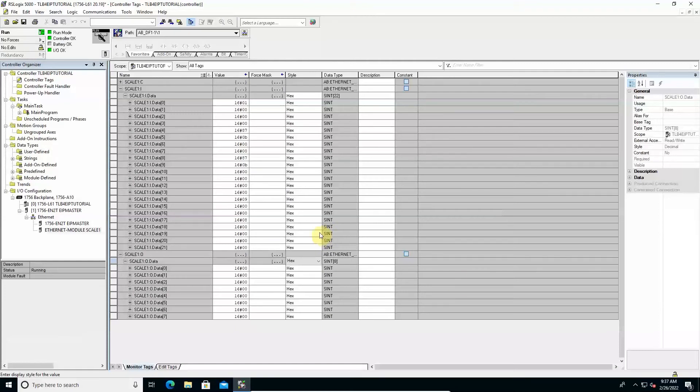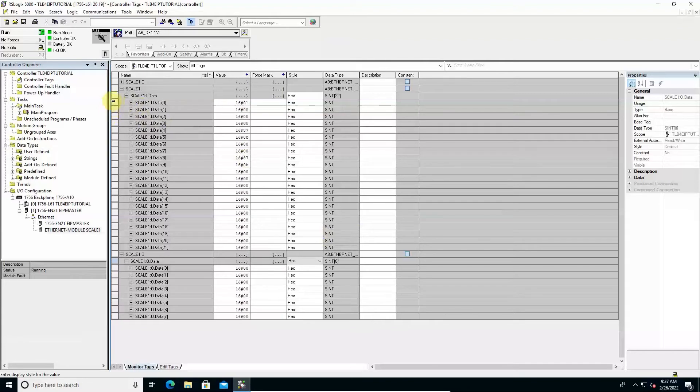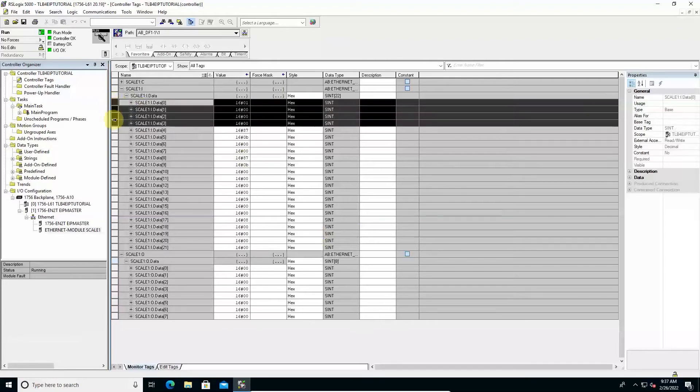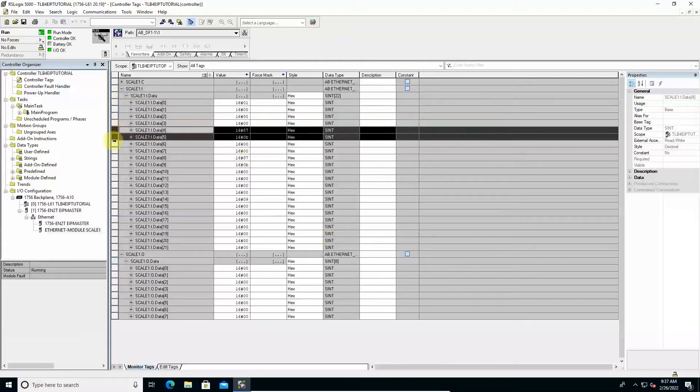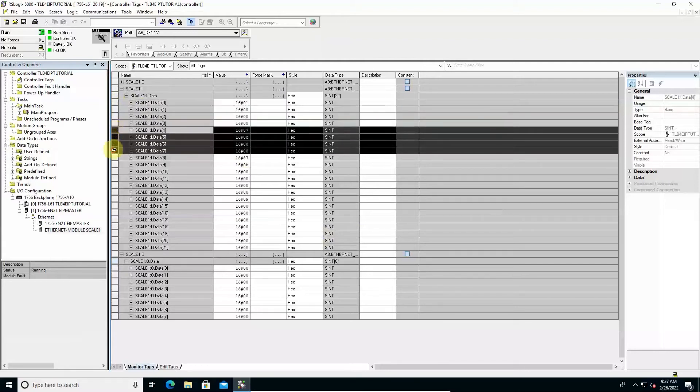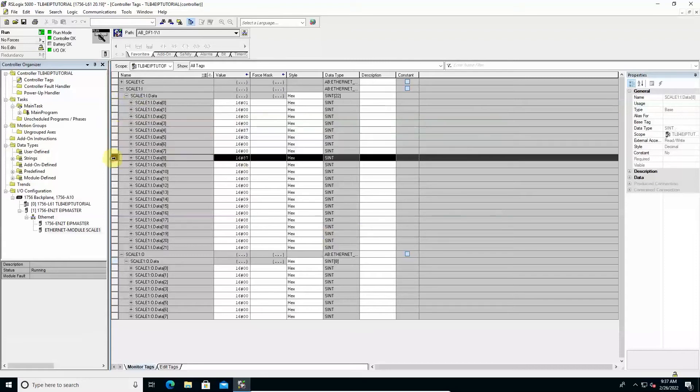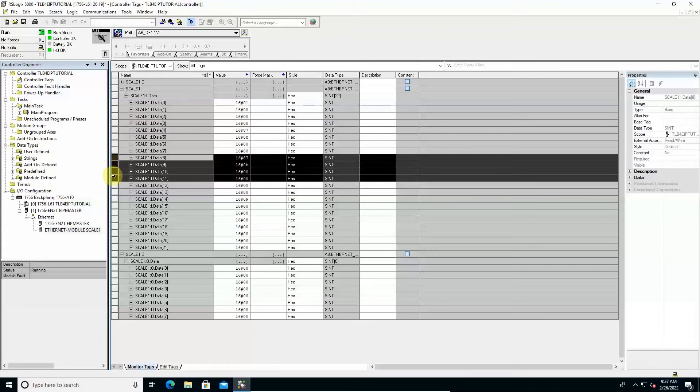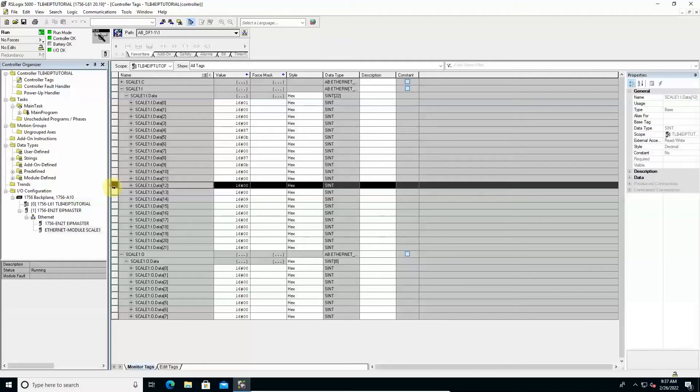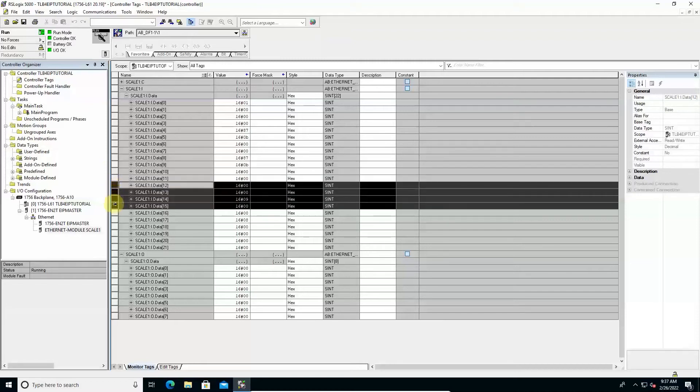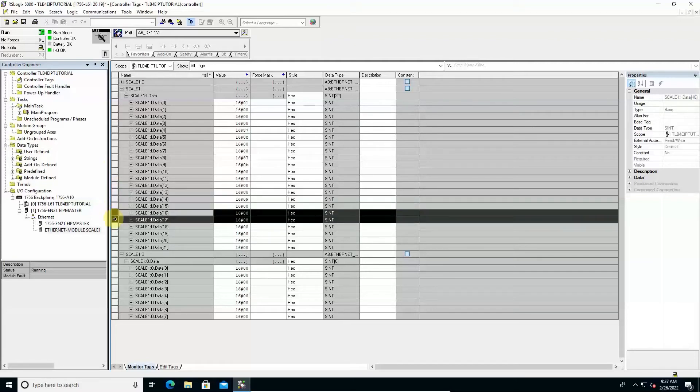Among the input data received by the PLC, we have the 4 bytes that make up the Ethernet IP header value, the 4 bytes that make up the current gross weight value, the 4 bytes that make up the current net weight value, the 4 bytes that make up the output exchange register, the 2 bytes that make up the status register value, and so on for the other parameters described in the table.